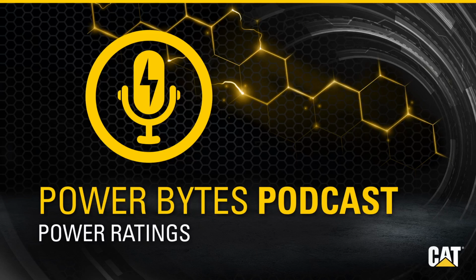Are there any standards organizations that help govern the genset rating categories? Yes, the International Standards Organization, or ISO, is most commonly referenced for reciprocating engines, and their standard, ISO 8528, is one of the most common standards we have. It has Part 1, which defines the application, rating, and the performance of a generator, and in the 2018 version, you'll find the power ratings section within Section 14 of that Part 1. Can you provide us with a brief overview of the rating categories that are defined by ISO?